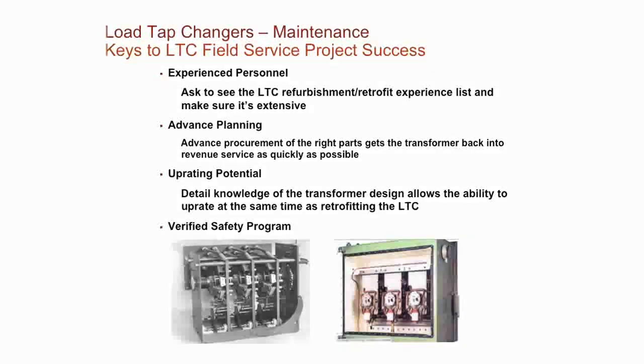Also, if you do an in-tank LTC, this is just a picture here. This is what we call the diverter switch. It drops down inside this tank here. And then below that is what we call the selector switch. But the diverter compartment is a separate compartment all of its own inside the transformer tank. That's where all the switching and arcing goes on inside this unit.